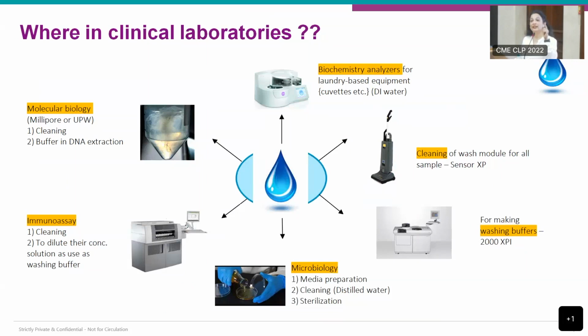So this is where maybe you are using dry chemistry, but you are still using water in some form, somewhere - for control, calibrator, or any clotting or other purpose. So maybe you are still using water substantially: cleaning of wash modules, then washing buffer getting made of DI - that is where the maximum utility happens, apart from your instruments.